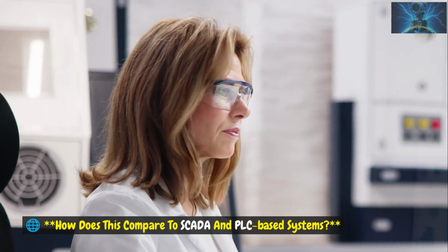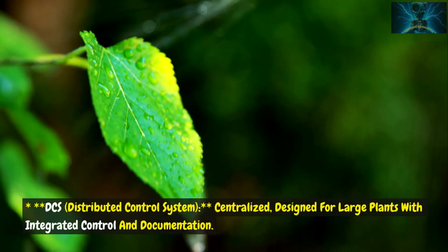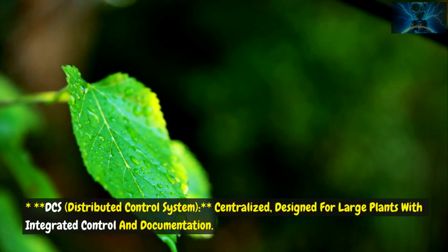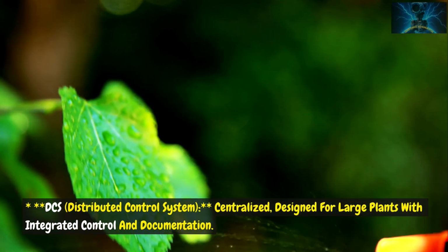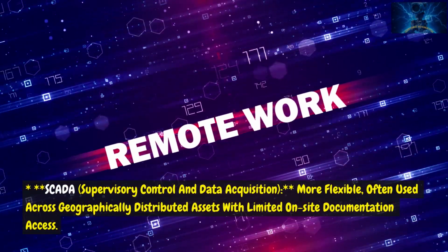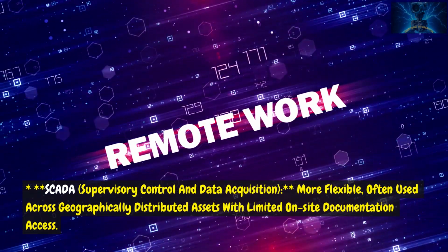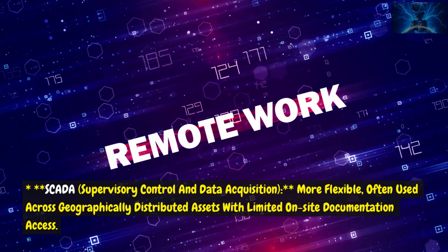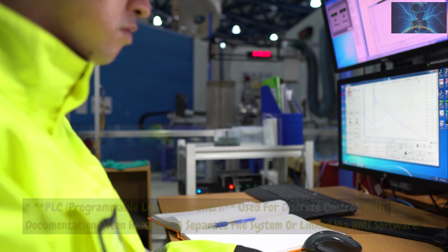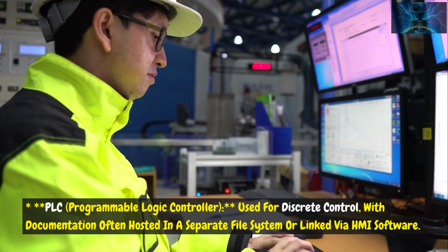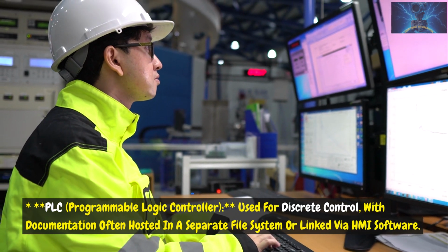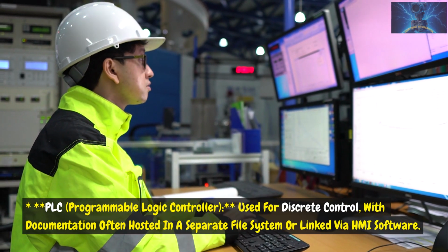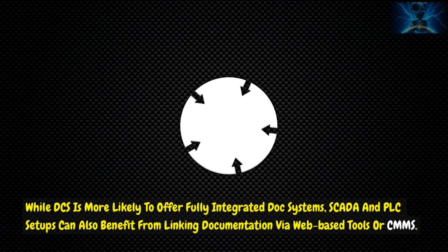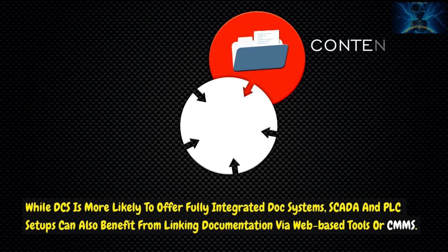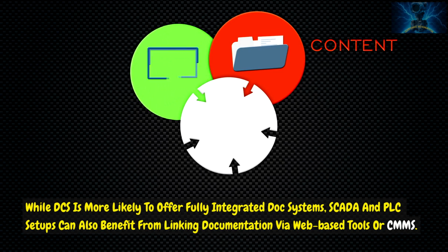How does this compare to SCADA and PLC-based systems? DCS, Distributed Control System, is centralized, designed for large plants with integrated control and documentation. SCADA, Supervisory Control and Data Acquisition, is more flexible, often used across geographically distributed assets with limited on-site documentation access. PLC, Programmable Logic Controller, is used for discrete control, with documentation often hosted in a separate file system or linked via HMI software. While DCS is more likely to offer fully integrated doc systems, SCADA and PLC setups can also benefit from linking documentation via web-based tools or CMMS.